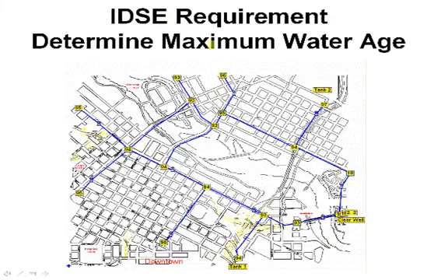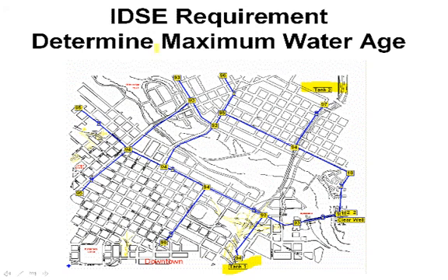Another analysis you can do is water age, which we need to do because of the EPA Stage 2 requirements. This shows the maximum water age in the system due to residence time in the tanks. In this particular system, the water age averages around 90 to 95 hours, except near the pump station where fresh water comes in from the clear well. This is an easy analysis to set up if you have a model.